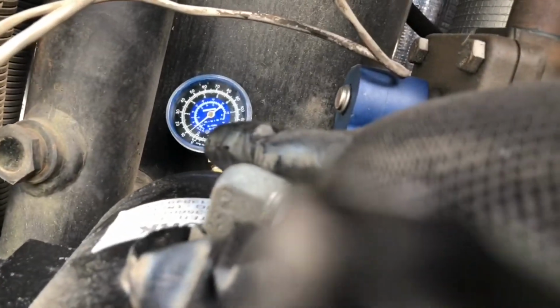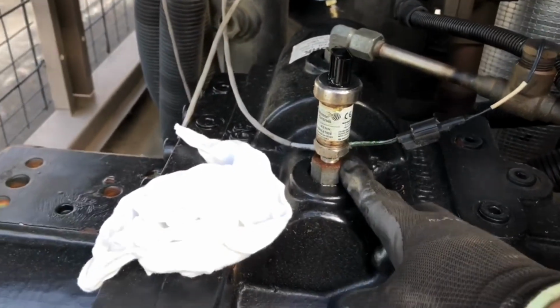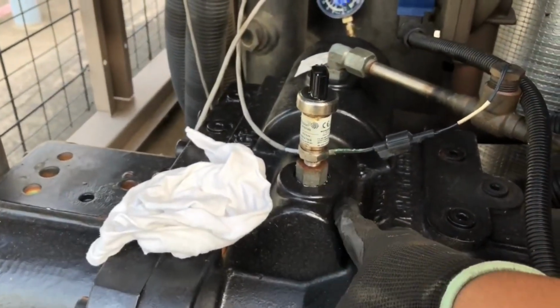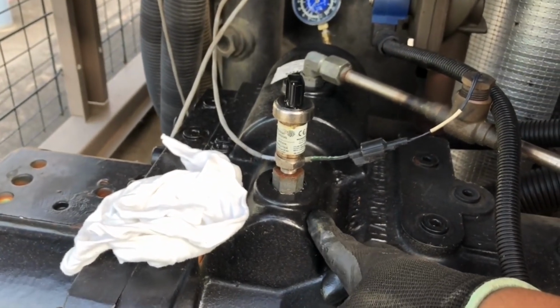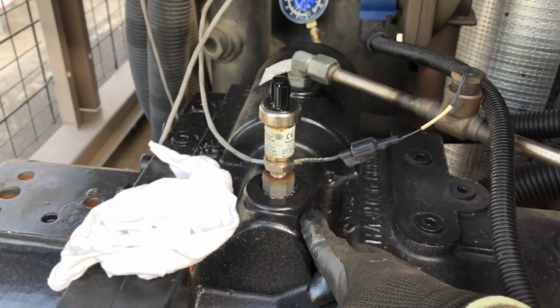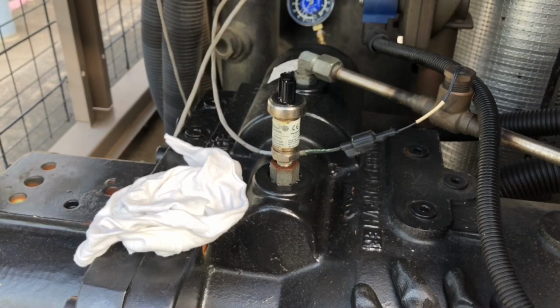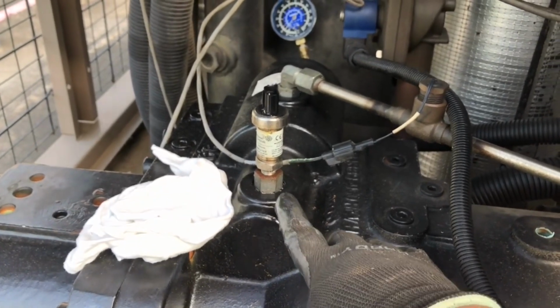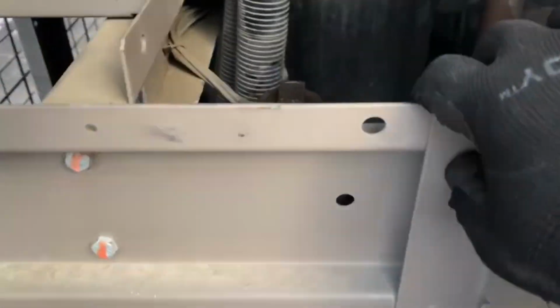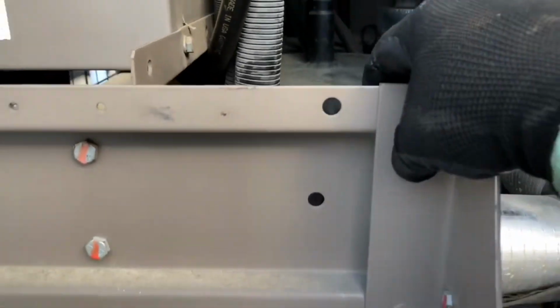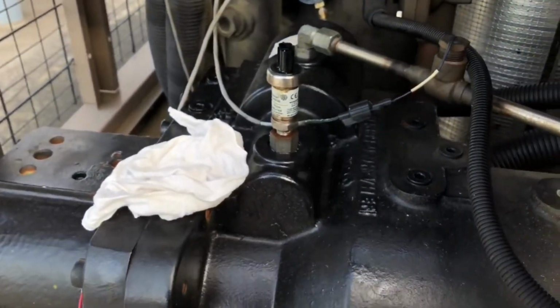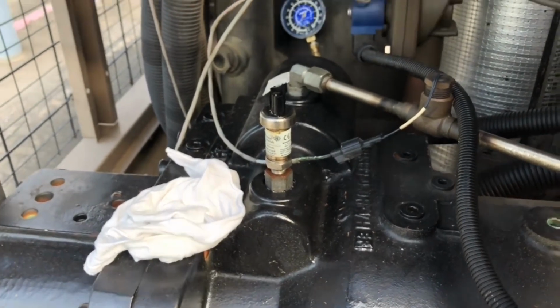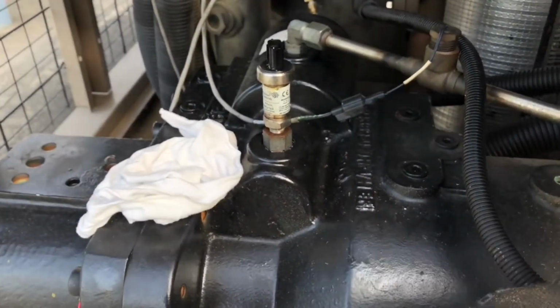Okay, so I took the pressure out. I still left, as you can see, a little bit over 10 psi on the system. The reason is when I take this off, I still have a little bit of pressure, and that way I can avoid the vacuum. Because I might not get a perfect vacuum if my valves are leaking a little refrigerant. I never get a perfect vacuum, so I'd rather have a little bit of pressure, and that pressure is gonna help me avoid getting any moisture. Those valves right there and this one over here, they might leak depending on the age of the system or the valves. They might age. So I'd rather leave pressure here and kind of avoid all that, especially if those valves are leaking.